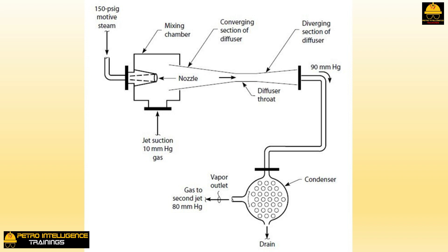Diverging compression, or velocity boost: as steam and gas leave the diffuser throat, they enter the gradually diverging sides of the diffuser and slow down. The kinetic energy of the flowing stream is partially converted to pressure — this is the velocity boost, which multiplies pressure by a factor of two or three. While smaller than the sonic boost, the velocity boost is more reliable. The overall pressure boost — the jet's compression ratio — is obtained by multiplying the sonic boost effect times the velocity boost effect.